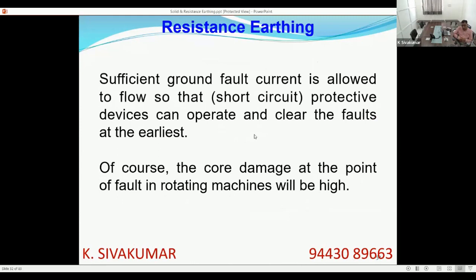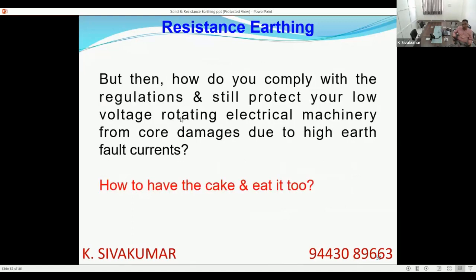Sufficient ground fault current is allowed to flow in solid grounding so that SCPD can operate and clear the fault. But since you are allowing the high fault current, core damage, if the fault happens within the machine core also, will get damaged. But then, how do you comply with the regulation? Still protect your low voltage rotating electrical machinery from core damages due to high earth fault current. So you have to have the cake and eat it too.